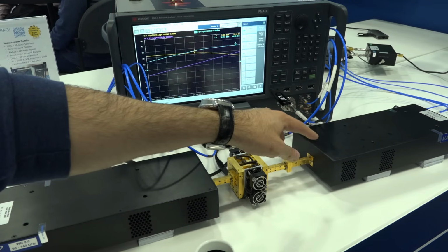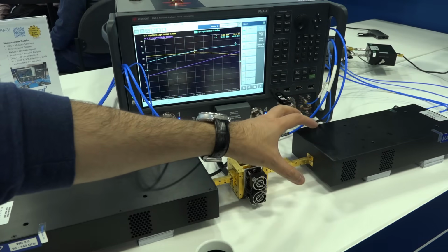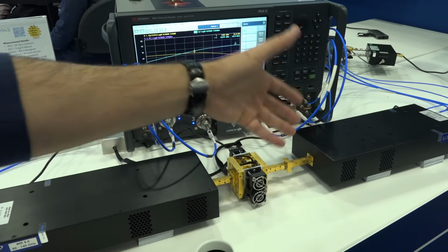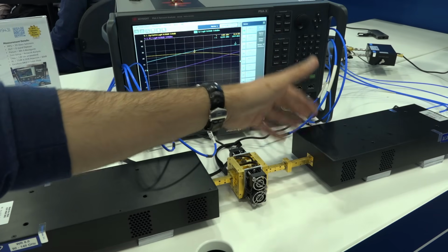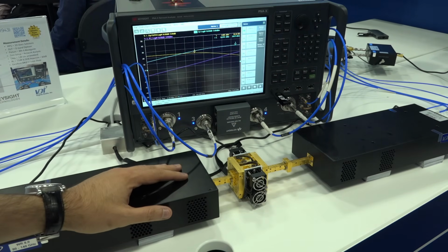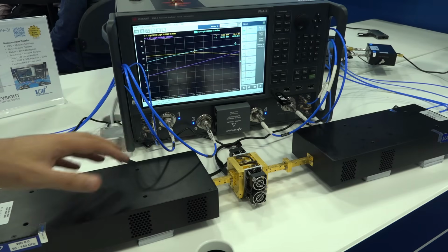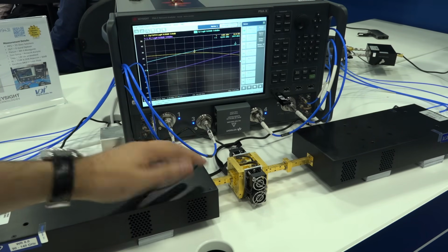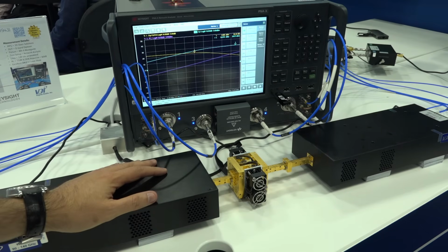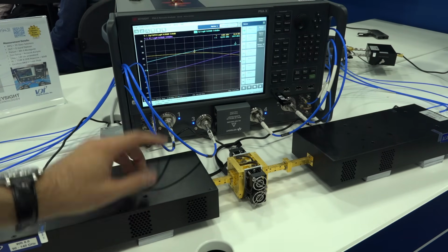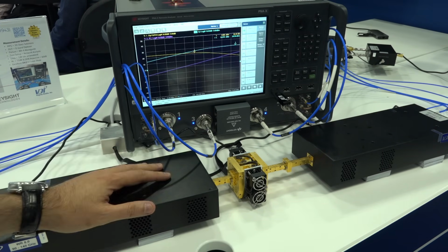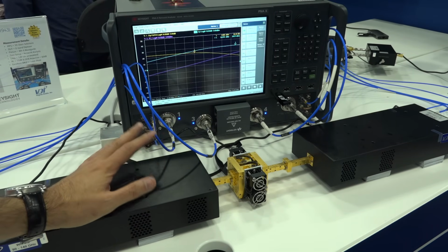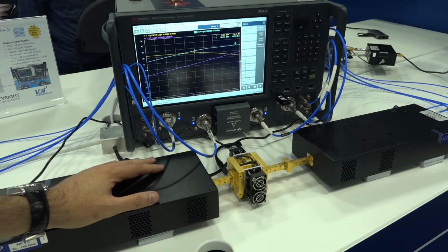So there are mixers on the other side and couplers that are optimized for just the right amount of coupling to maintain the dynamic range you want on the receiver while being able to accept that 30 dBm incident power into the TR headset. I think this is the first time I've ever actually seen a 1 watt TR headset here, using completely end-to-end custom design indium phosphide devices to be able to do this. But these high-power TR headsets are going to be the de facto for both active measurement as well as passive measurements in these really high frequency ranges.